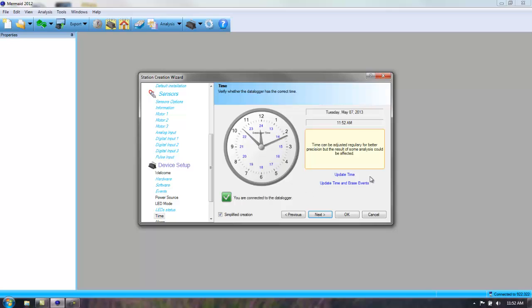This is where you would update the time or update the time and erase the events. The difference is when you update the time and erase the events, any data that you had previously stored in the particular data logger that you're setting up will erase all the events in that recorder. And that's what I like to do each time. Start fresh.